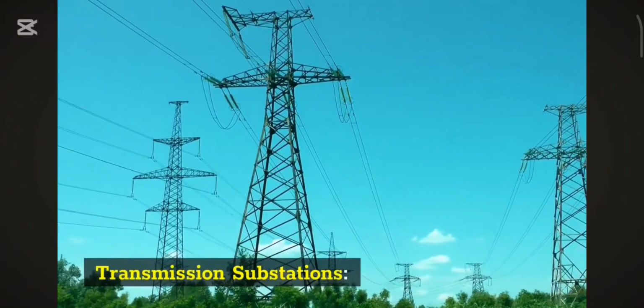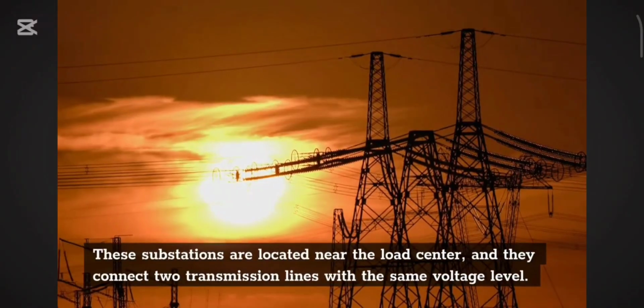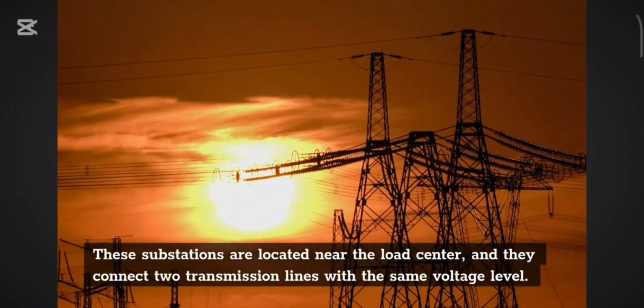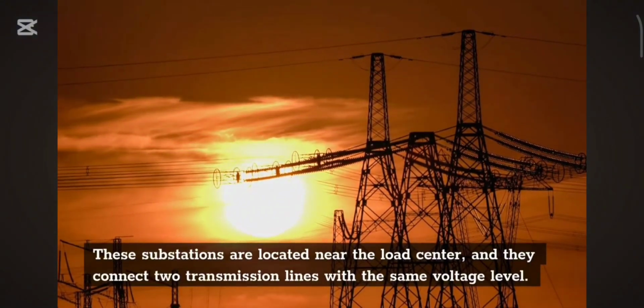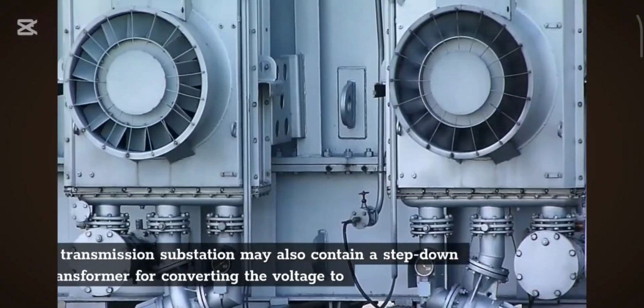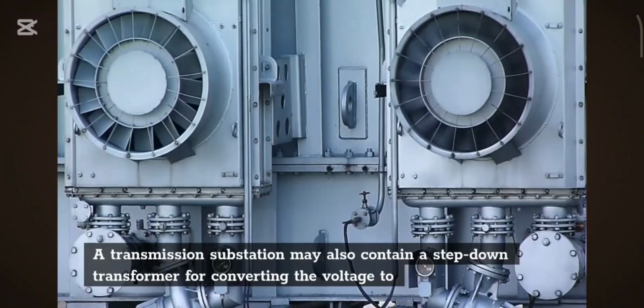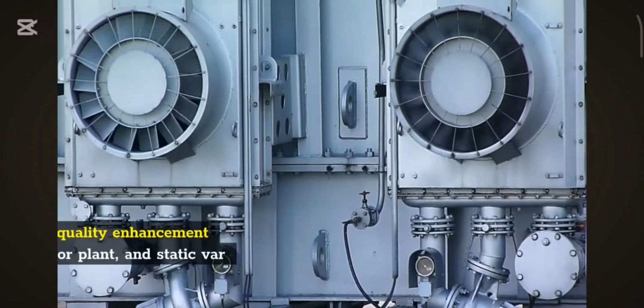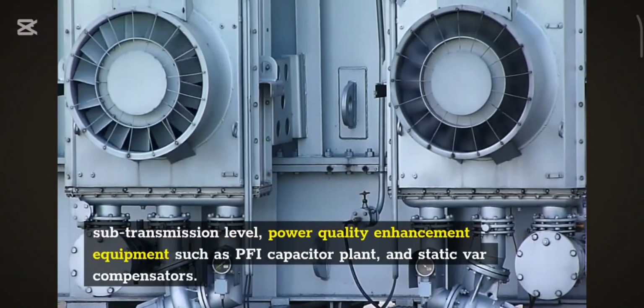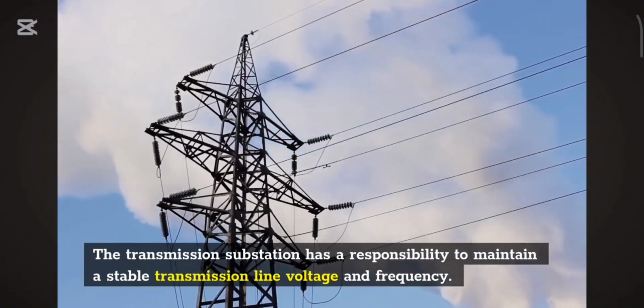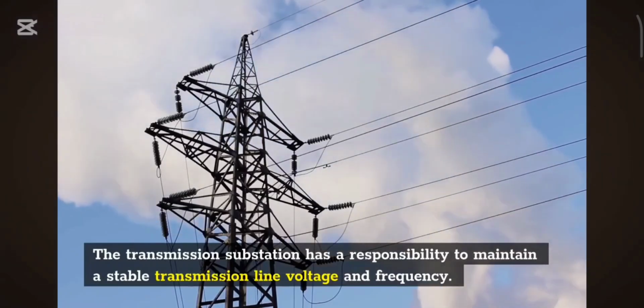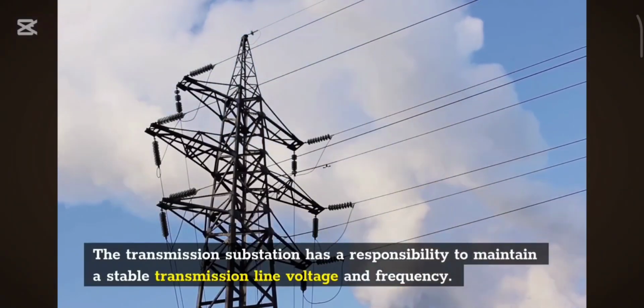Transmission substations. These substations are located near the load center, and they connect two transmission lines with the same voltage level. A transmission substation may also contain a step-down transformer for converting the voltage to sub-transmission level, power quality enhancement equipment such as PF capacitor banks, and static VAR compensators. The transmission substation has a responsibility to maintain a stable transmission line voltage and frequency.